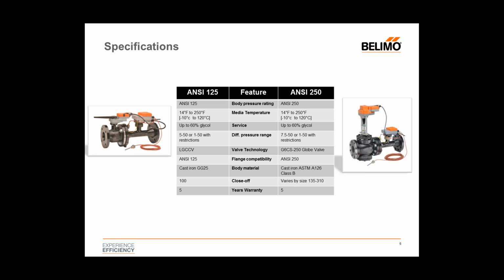I'd like to cover some of the specifications with you now. I'm contrasting these with the ANSI 125 because some of you may be familiar already with our ANSI 125 version ePIV and energy valve, so I'd like to make that correlation to make the transition a little easier for you. As far as the body pressure rating, it is fully compliant with ANSI 250 specifications as opposed to the ANSI 125 versions. The media temperature is identical for 125 and 250: from 14 degrees Fahrenheit to 250 degrees Fahrenheit, or minus 10 degrees C to plus 120 degrees C. Service: they're both capable of water and up to 60% glycol, pretty constant within our valve range.